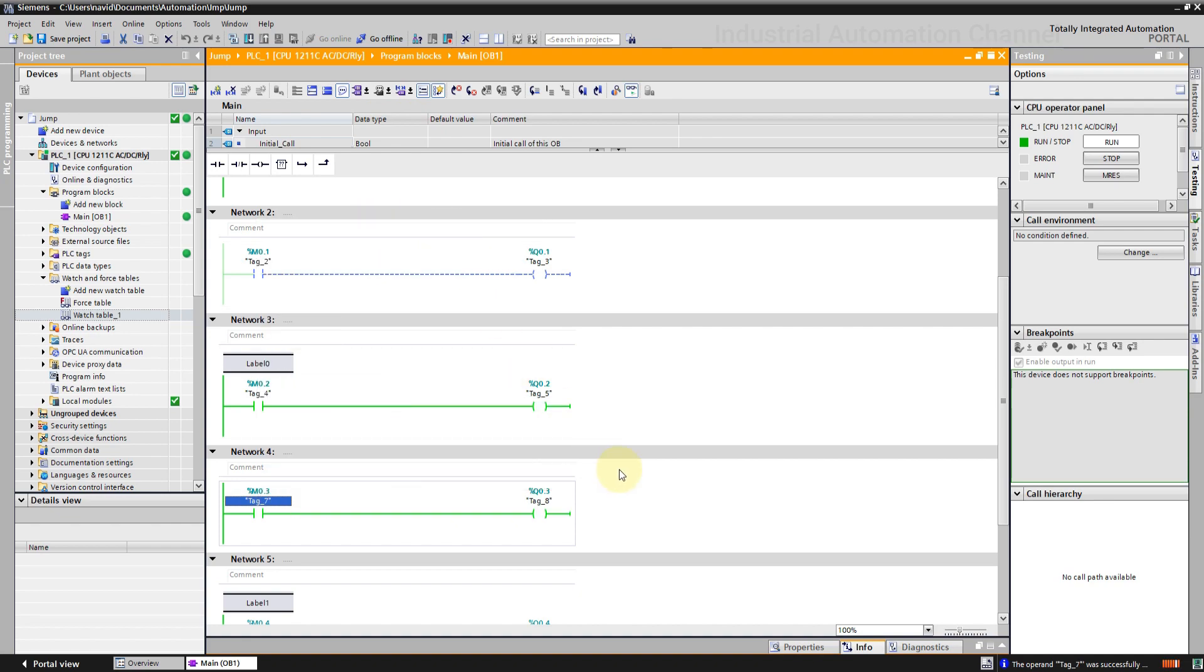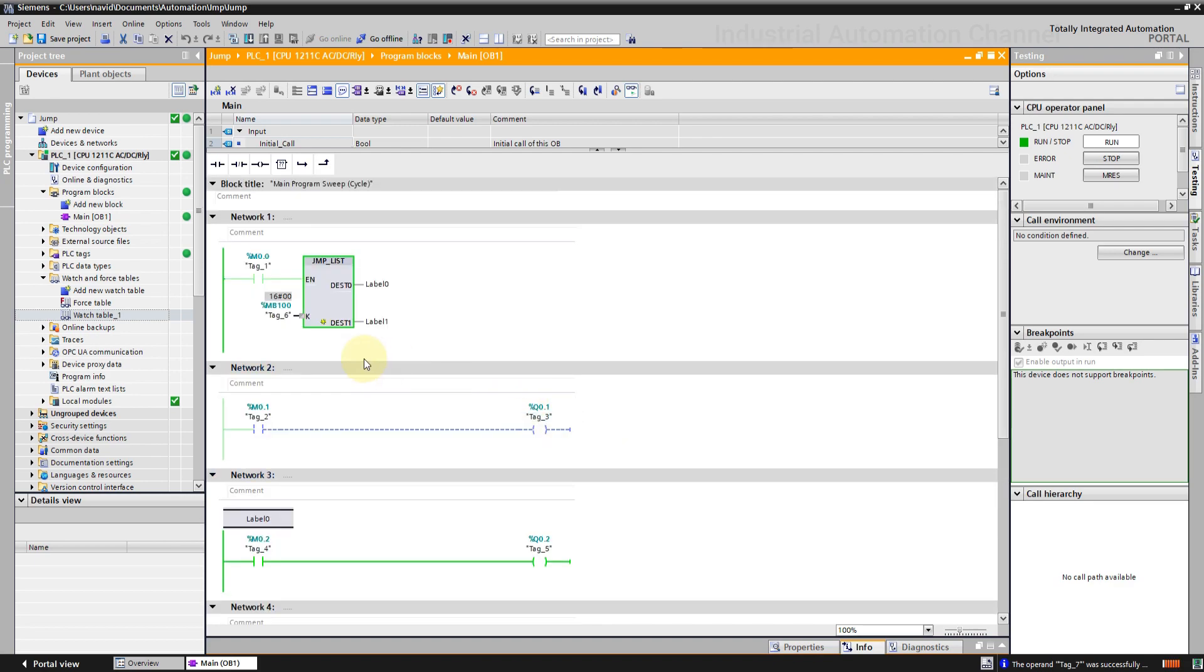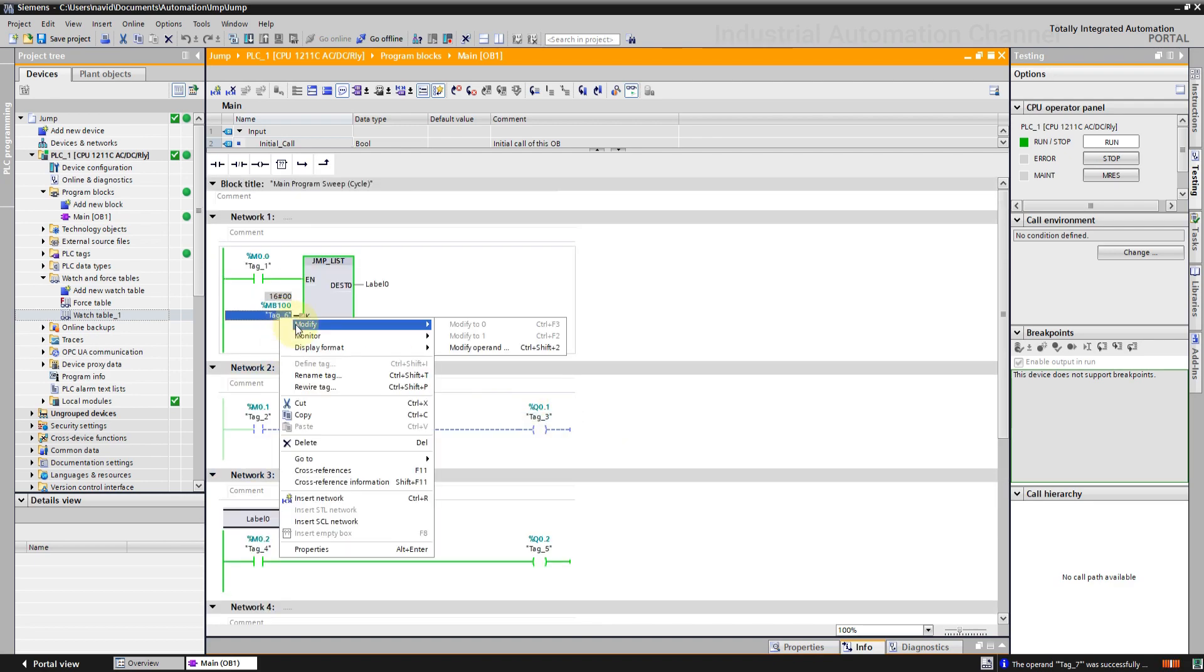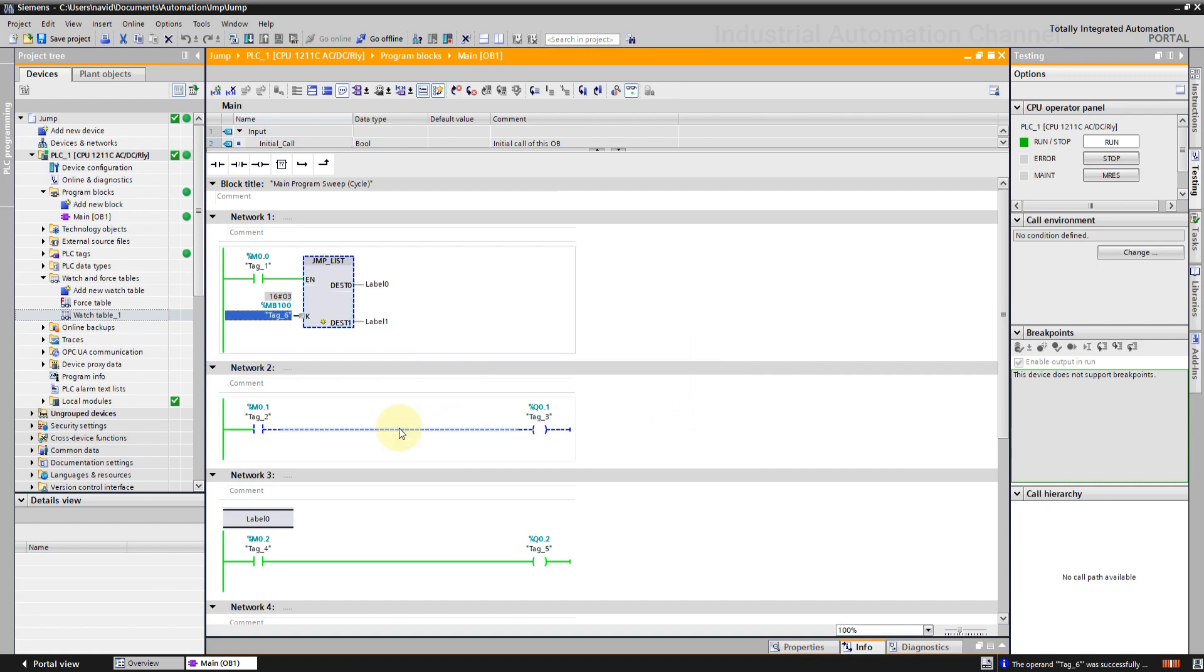We can define maximum 32 destinations. Be careful if the value of the key is greater than the number of destinations. The program execution will be resumed in the next network. For example, if we have two destinations but the key value is 3, then the next network will be executed.